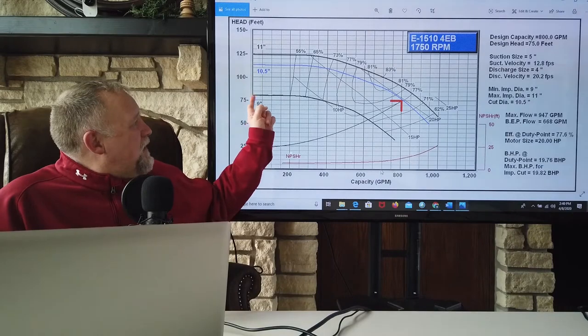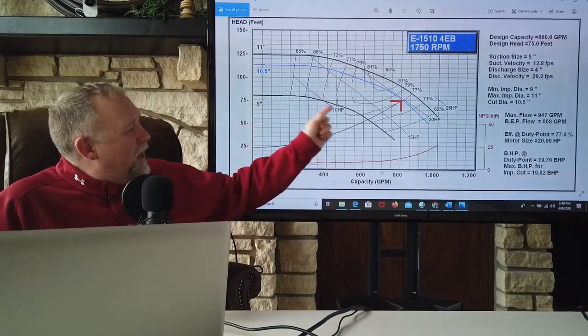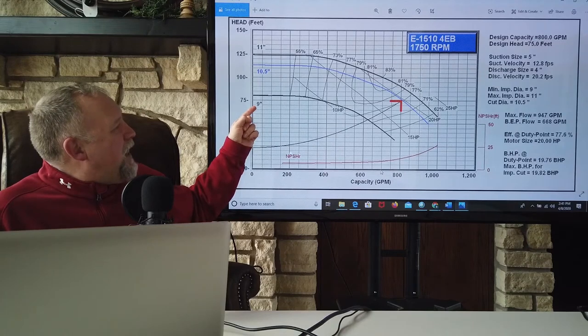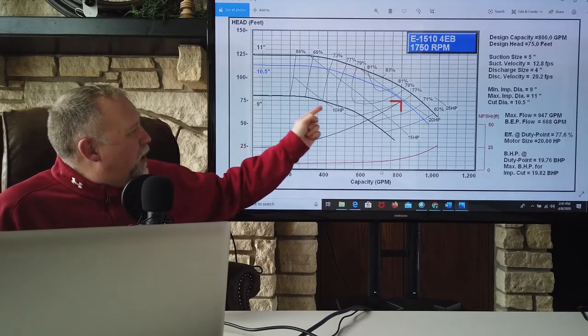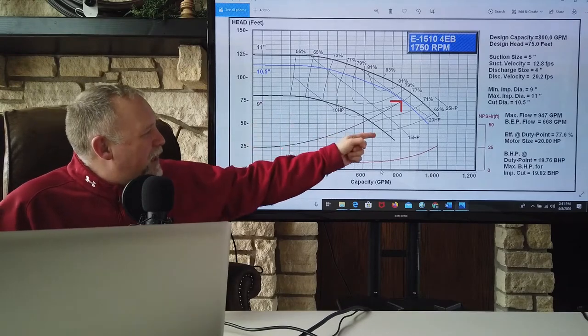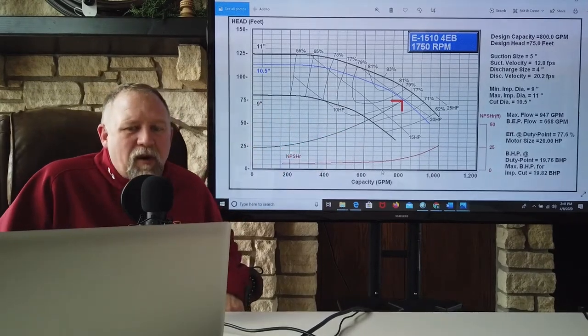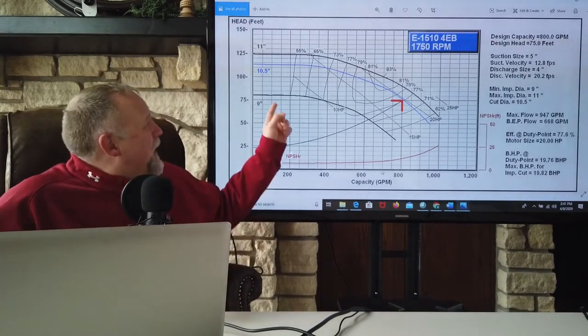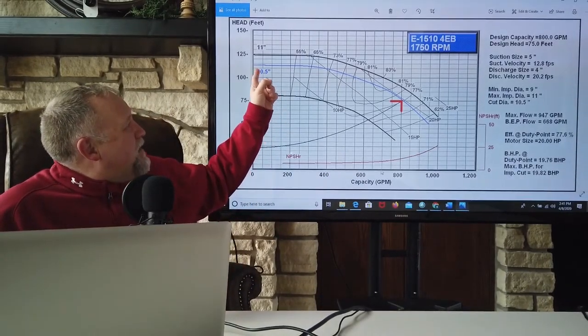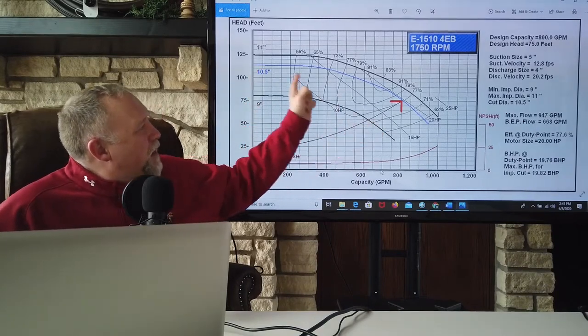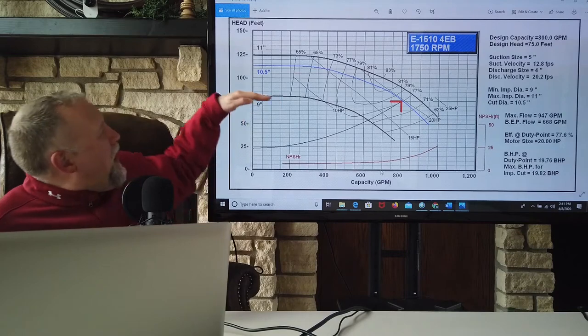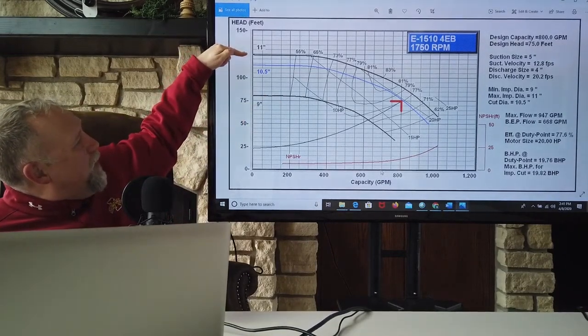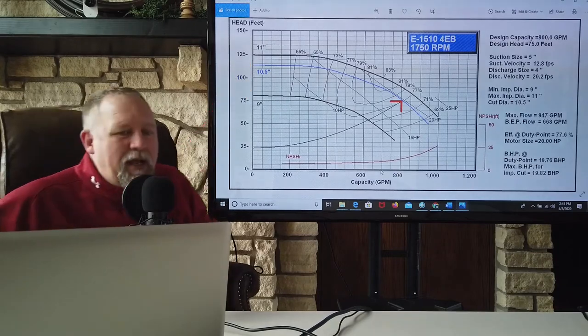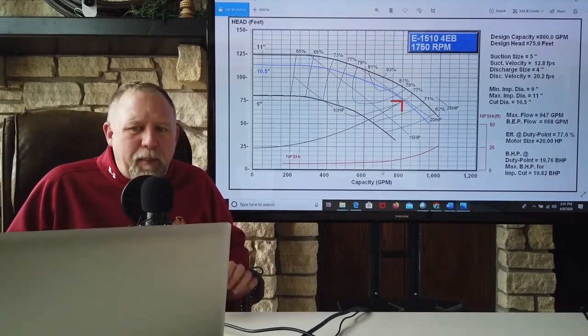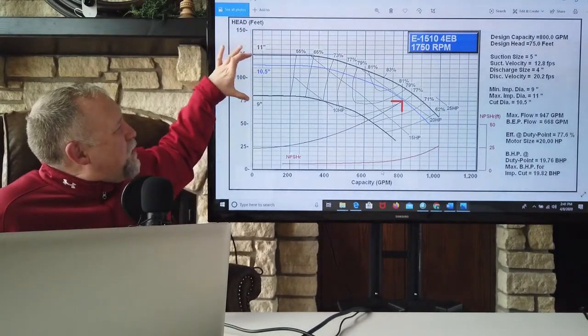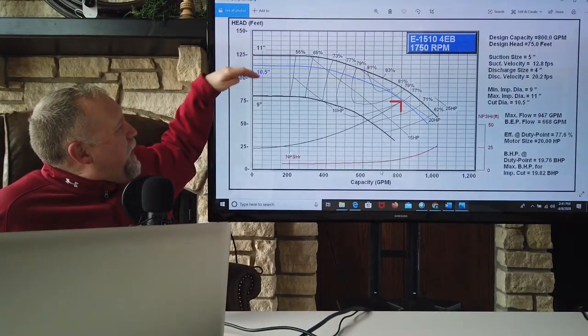Now notice, these curves that go this way, these are impeller curves. This is, for a 9-inch impeller, it can develop all of these possible combinations of flow and pressure. Now, if we had the same pump case and we increase that to a 10.5-inch impeller, that's this blue line that goes down there. Those are all the possible combinations of flow and pressure. And if we took it all the way up to an 11-inch impeller, those are all of the possible combinations. And for a given pump casing, that's this range, it could have a range of impeller sizes.